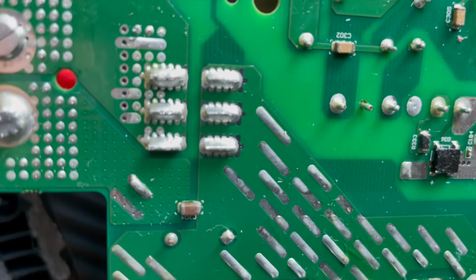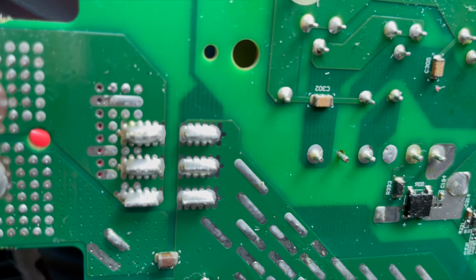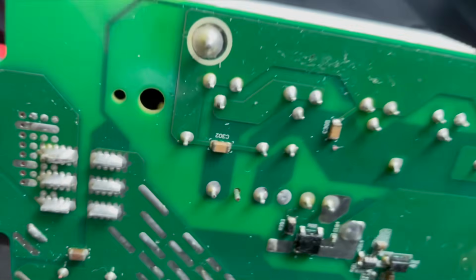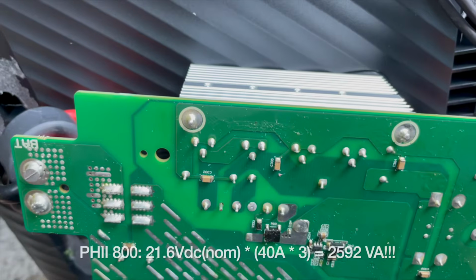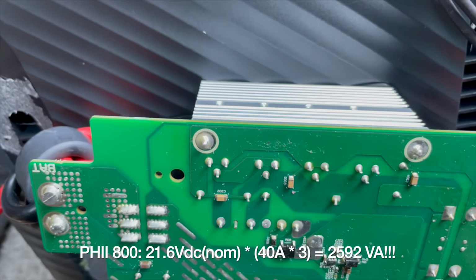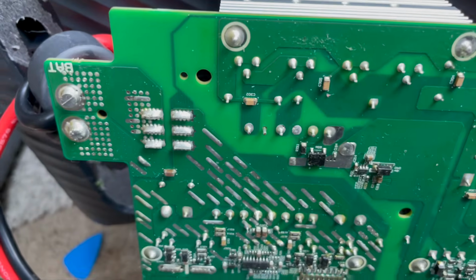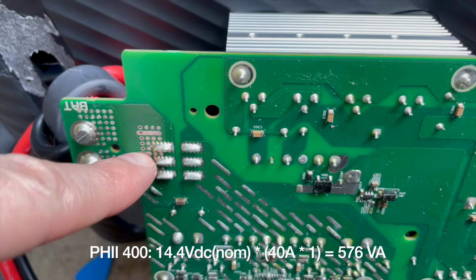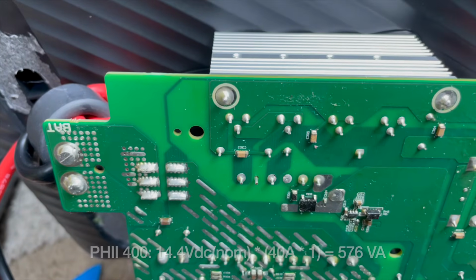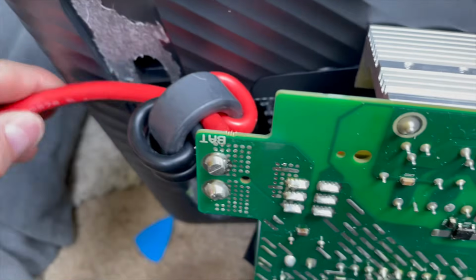No, there's no split in that track. So those 3 fuses are all together in parallel, that's 120 amps in parallel. I'll have to do the calculations, but that's way more than I thought. For reference, the PowerHouse II 400 had one 40 amp fuse, so this is beefy, which explains why this wire gauge is so massive.